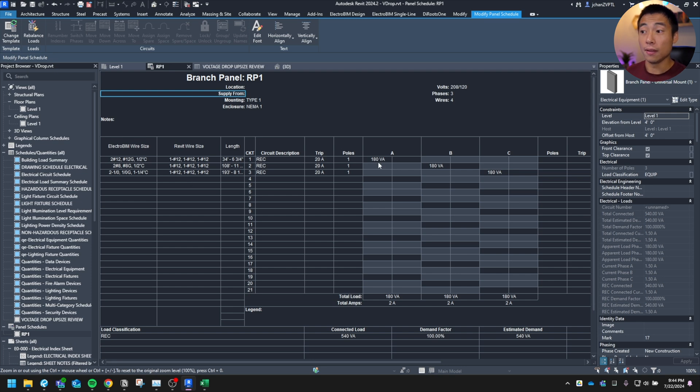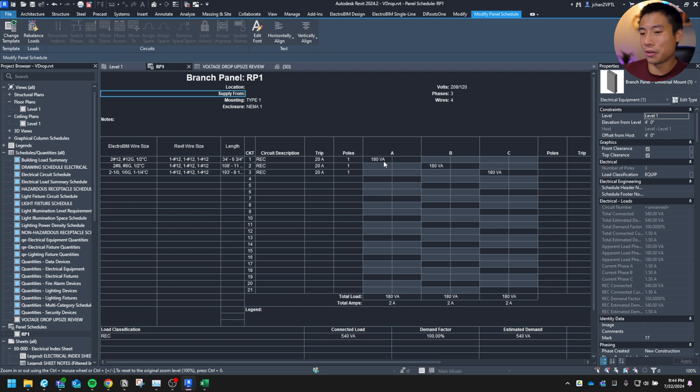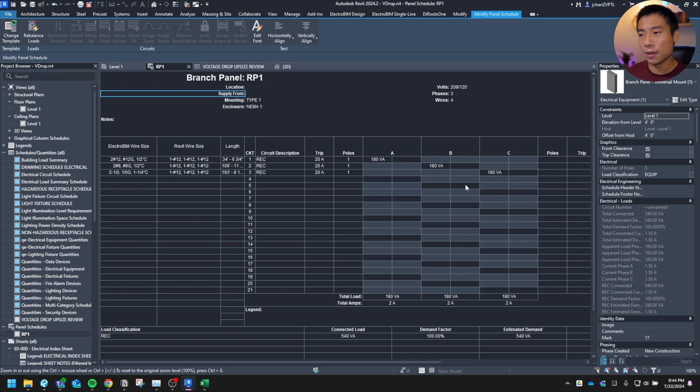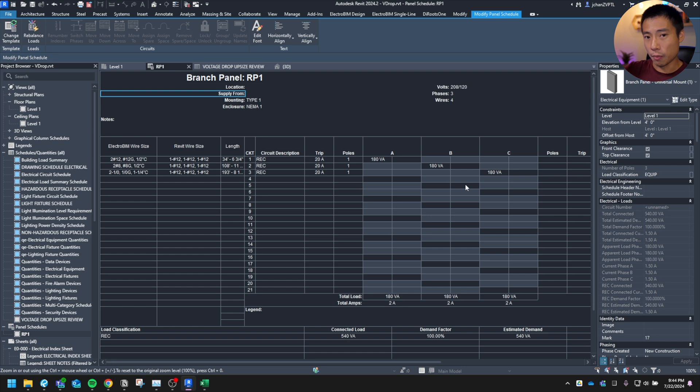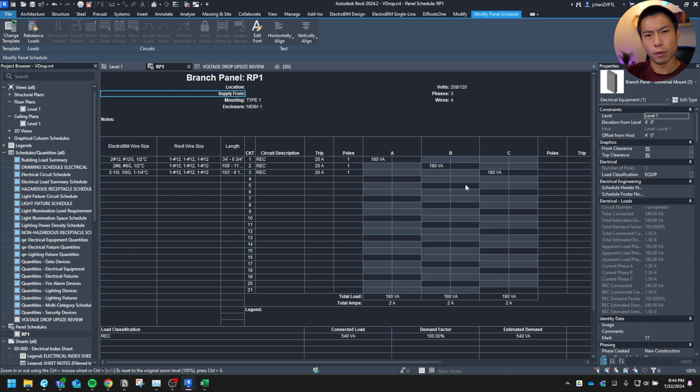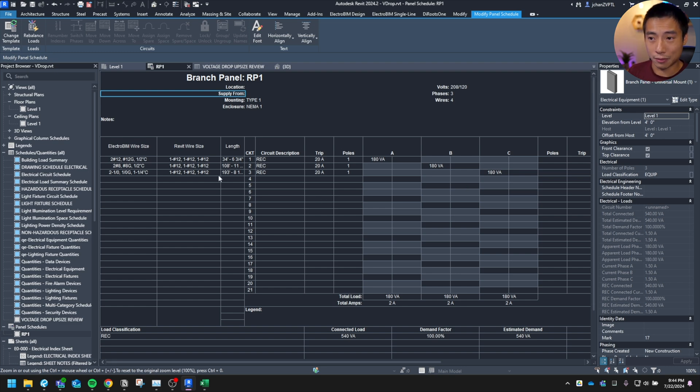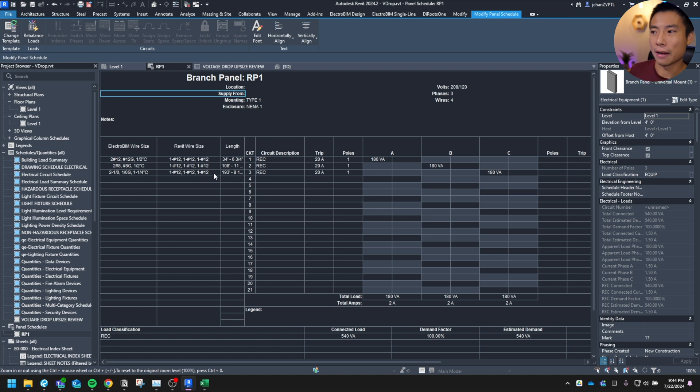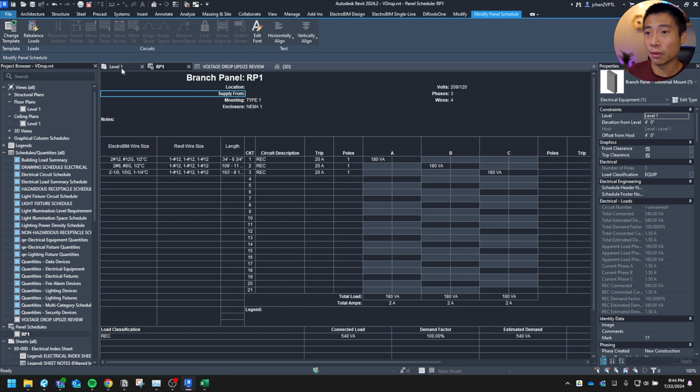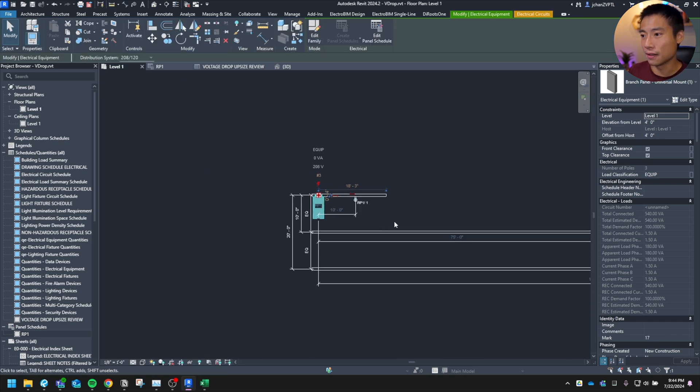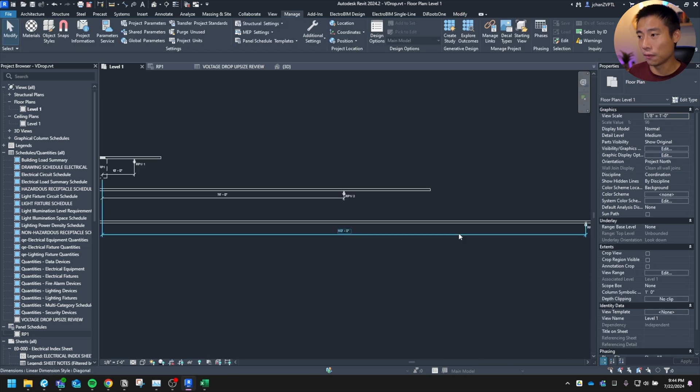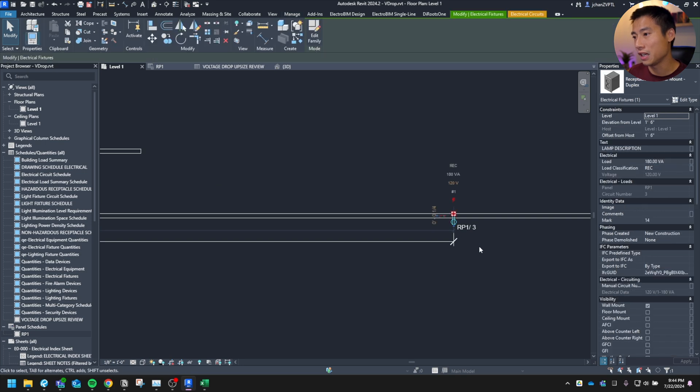You can see that it's a 20 amp circuit, single pole, 180 VA and Revit thinks everything is fine at number 12. That's because these were circuited as general receptacle. And that's typically what they come in at 180 VA. We didn't really have an equipment in mind, but because my one circuit was a rooftop equipment maintenance circuit. So like within 25 feet of maintainable equipment on the roof, you have to have a general receptacle. So we put in a general receptacle and it landed with 180 VA. So Revit does this just fine. It's like, hey, it's fine. You can use a number 12. You don't have to worry about it.